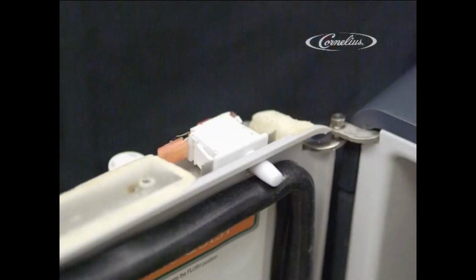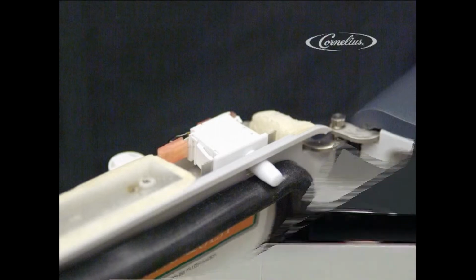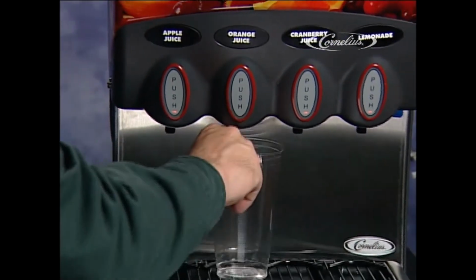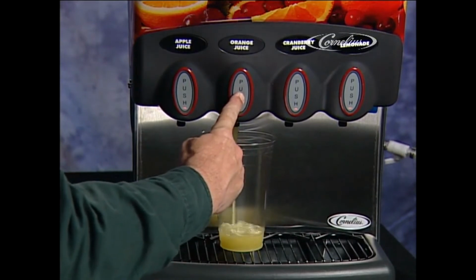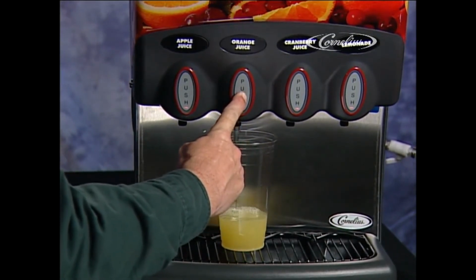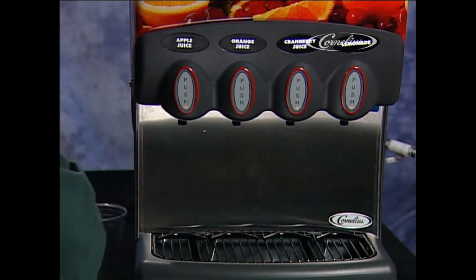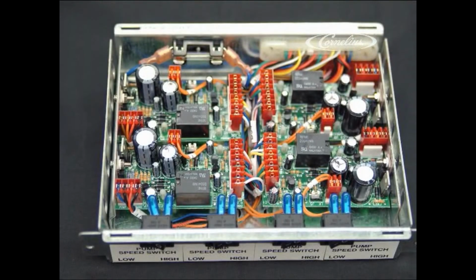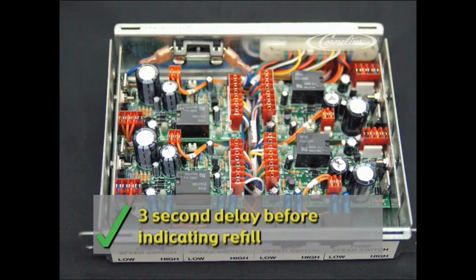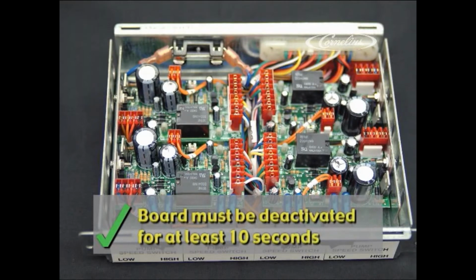When the door is opened, the reset door switch cuts the 26 alternating current voltage to the electrical box and the VRB boards. The concentrate package is loaded and the pins are covered again. When the door closes, the switch engages the 26 volts AC to the E-box. With the concentrate itself completing the circuit, the system is activated and the light goes out. Every VRB has a 3-second delay before the system indicates refill, so as to accommodate any small interruption in concentrate flow, such as an air bubble in the bottle. Upon resetting, the VRB board must be deactivated for a period of at least 10 seconds, or about the time it takes to remove the old package and replace it with the new. Any time that is shorter than 10 seconds, the VRB will not reset and the refill light will remain on.